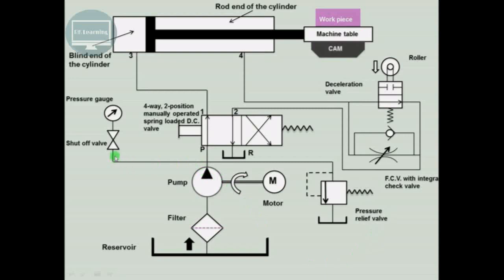There is also a shut-off valve connected to the pressure gauge, which indicates the circuit pressure. If the pressure exceeds the design pressure, some of the fluid will go to the relief valve, flow to the reservoir, and the system pressure is restored back to the original value.